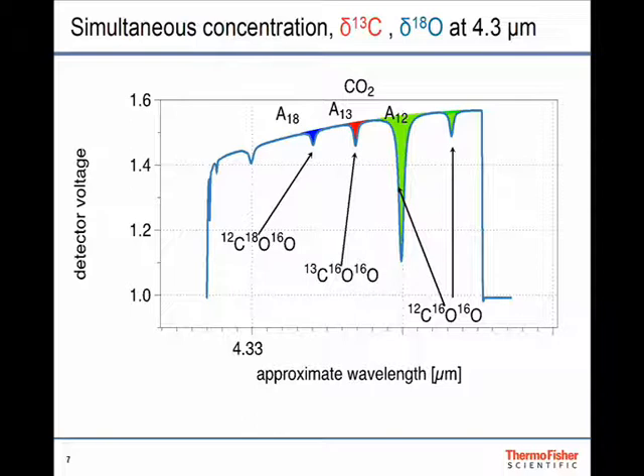Another thing to keep in mind is we scan these spectra. We scan the laser internally at 500 Hz. So every two milliseconds we get an isotope ratio. Well, except we can't fit that fast, so we actually average for one second. But it's truly an average of one second and of each line. So there is no worry about rapidly changing concentrations or isotope ratios. That would get weird results if you sit on this line for a while and then on that line. We continuously scan the laser.